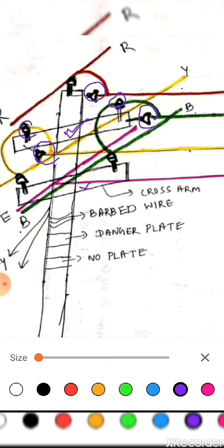Here 2 stay sets complete are connected to the existing pole for the mechanical strength of the pole, because the new 3 lines or 4 lines are taken from the existing 11 kV line. Next is concreting of the existing pole. For more mechanical strength, the pole should be concreted again. The quantity is 1 number.